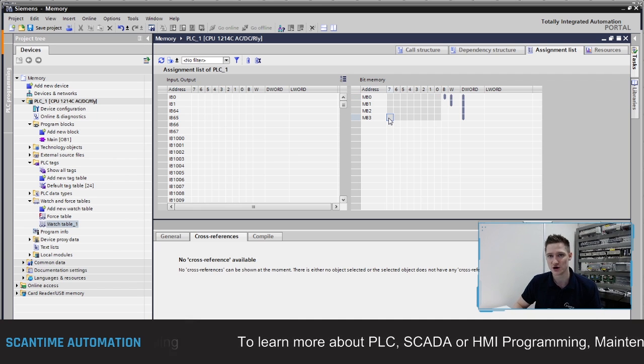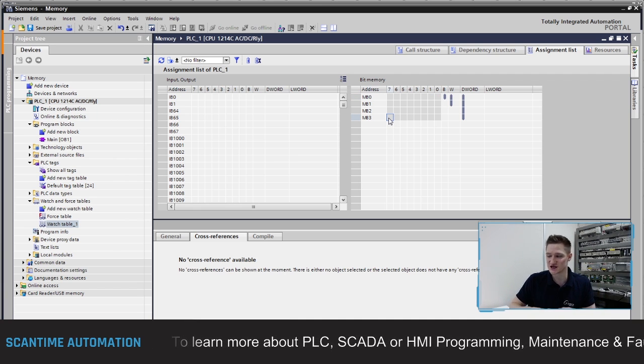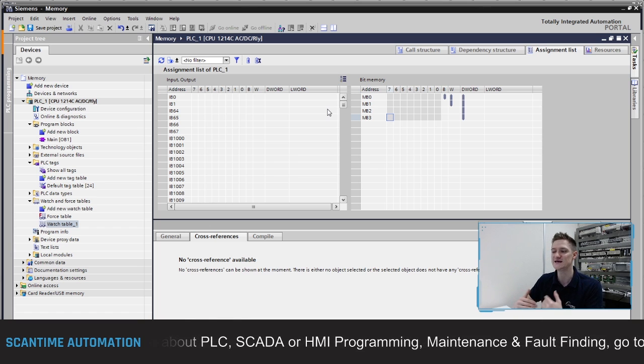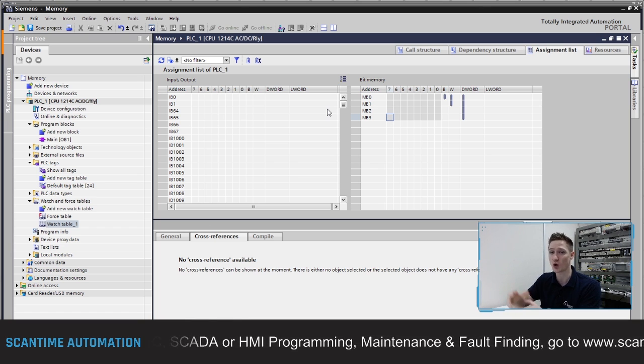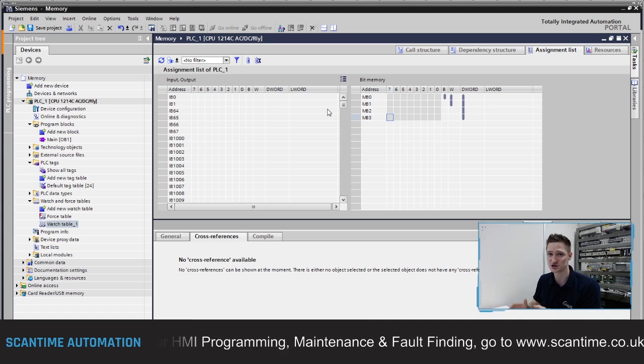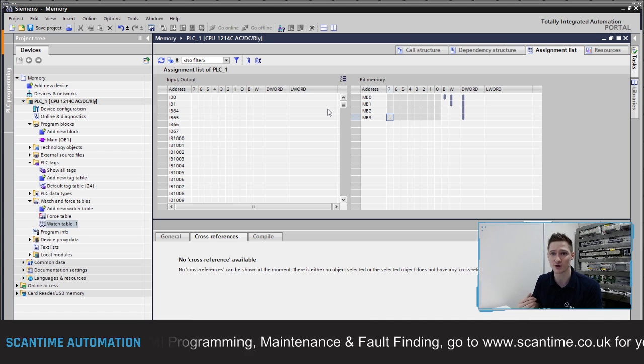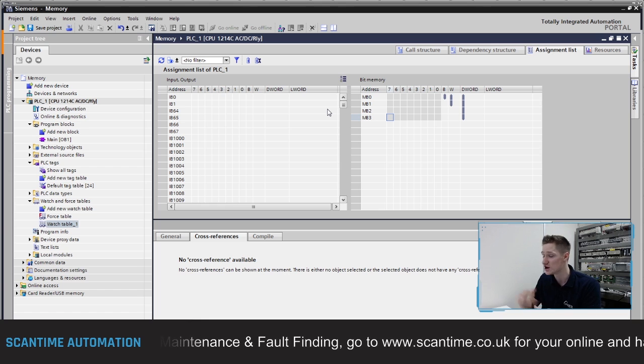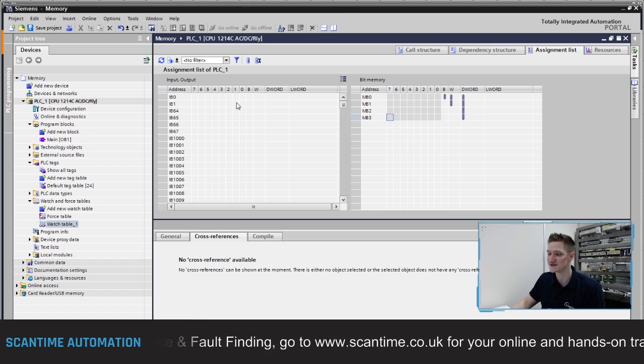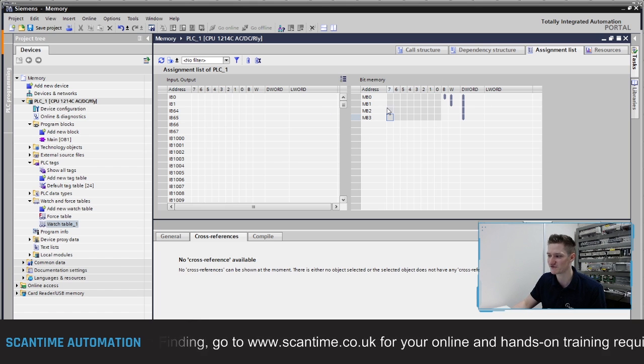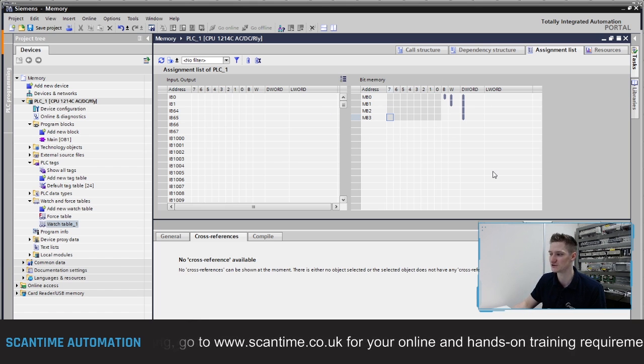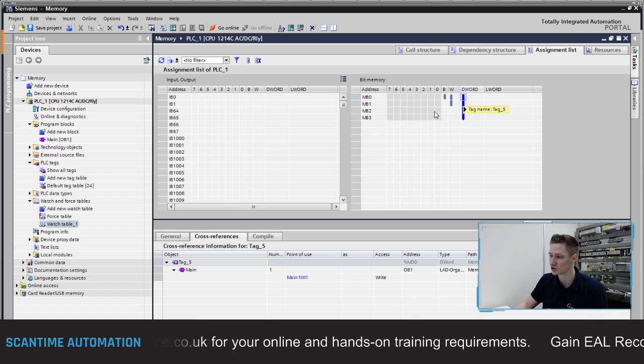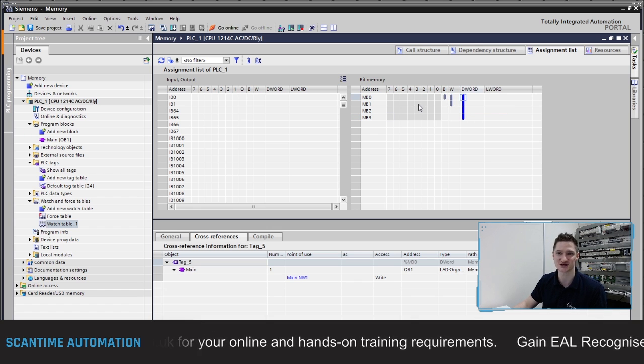When you're actually working with Siemens internal memory, you've got to be very careful because it's easy to just use addressing that's already being used. The best thing to do whenever you want to use internal registers is to check the Assignment List and verify it's not already being used, because as we can see here we're actually overwriting these addresses multiple times inside of the program.